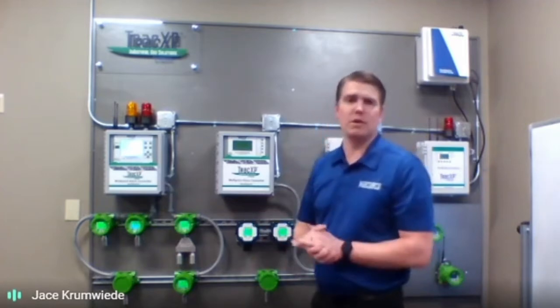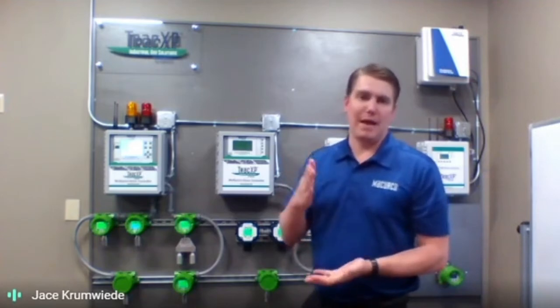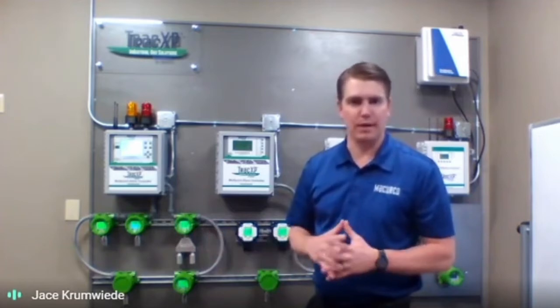Right here in the black, you'll see polycarbonate. So these are Class 1 Division 2 non-incendive units. So they will not provide that explosion-proof rating, but they will still allow you for a washdown rated type unit. And again, you'll have a multitude of different sensors, different gas types available within those products.